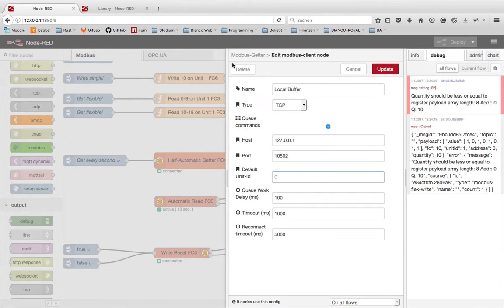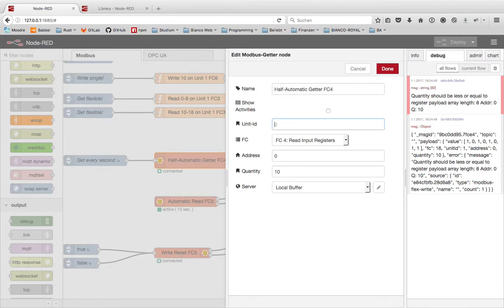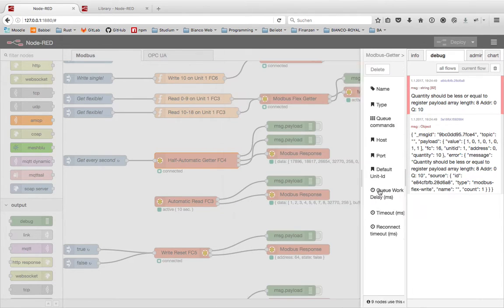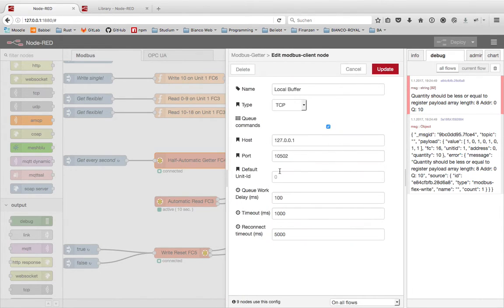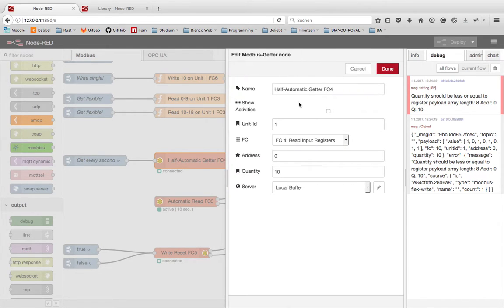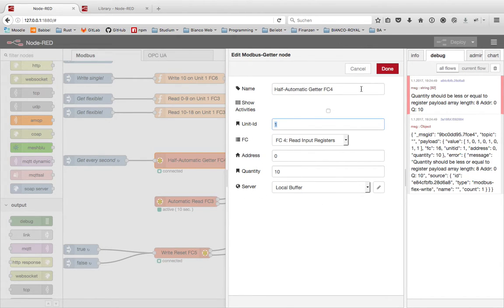If here it is zero and at your incoming node it is zero then it will be zero. But when you say here I want to write to unit ID one then it will be sent the message with unit ID one. And then this will not be used. Also if you say here it's unit ID two for all other nodes, but when your node says I want to use unit ID one then it gets one. This value always overwrites the value in the server communication.